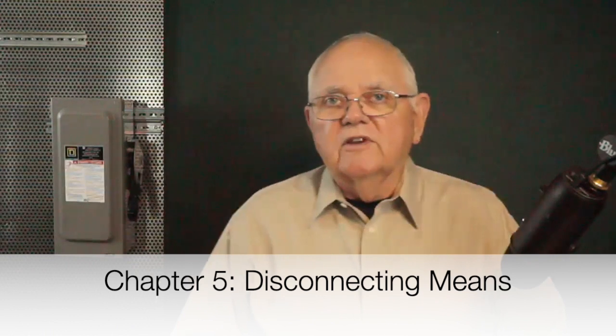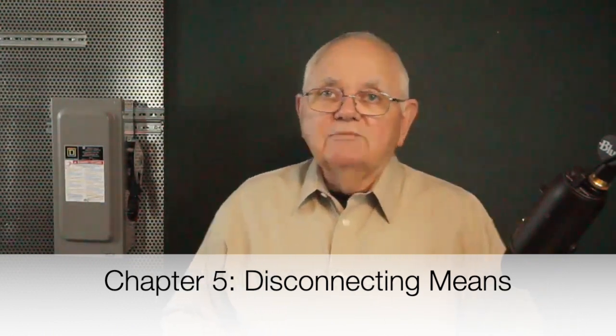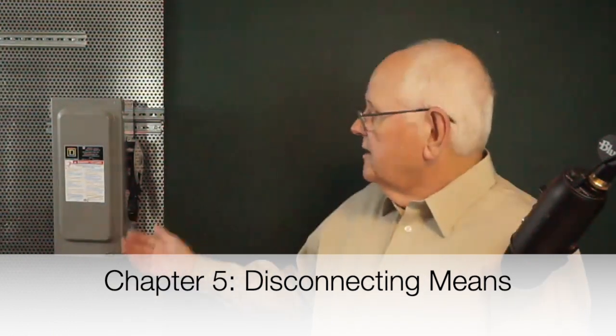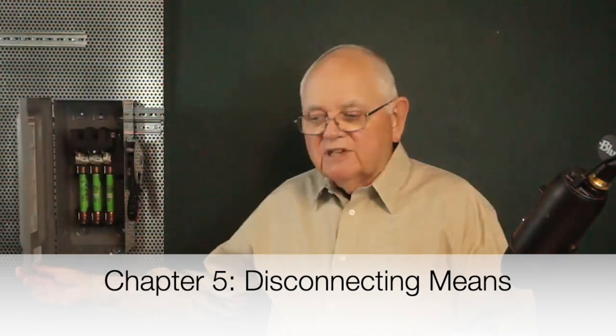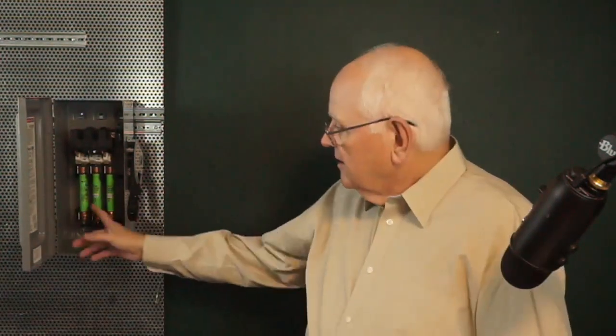Now let's begin talking about chapter 5, where it starts to go into the disconnecting means. We can have different types of disconnects. This is our standard old disconnect you've seen used in other tech talks. It's a 3-pole, with 3 fuses on the inside, so it's a fuse disconnect, rated for 600 volts. A disconnect like this we would see maybe on the outside or top of an industrial machine. There are requirements as to where we're going to place it.